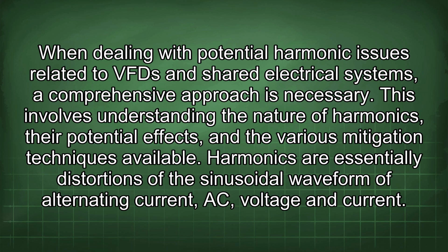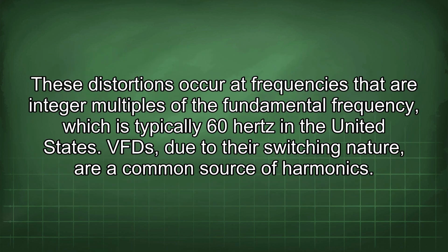When dealing with potential harmonic issues related to VFD and shared electrical systems, a comprehensive approach is necessary. This involves understanding the nature of harmonics, their potential effects, and the various mitigation techniques available. Harmonics are essentially distortions of the sinusoidal waveform of alternating current (AC) voltage and current. These distortions occur at frequencies that are integer multiples of the fundamental frequency, which is typically 60 Hz in the United States. VFDs, due to their switching nature, are a common source of harmonics.